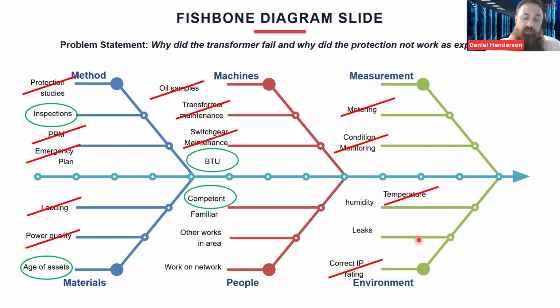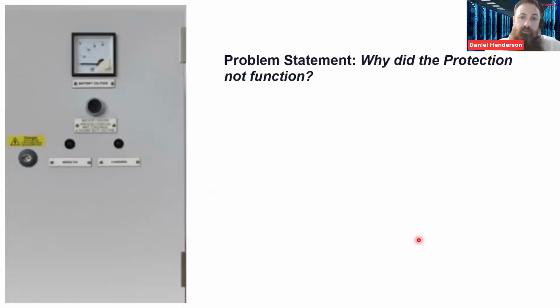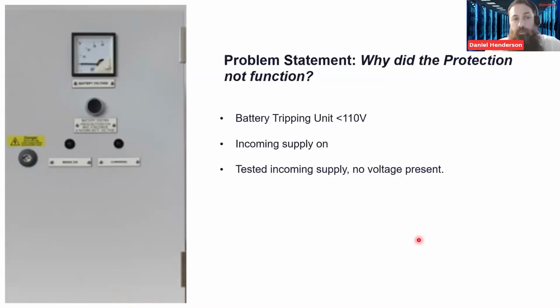Well, what I've had to do at this point is, because the transformer failed, make sure that that doesn't happen again in terms of electrical safety and reliability. So I'm trying to figure out why the protection didn't work. I've gone to check the batteries. I've checked the float voltage and I'm getting less than 110, which maybe is an impact from the downtime. I've checked the incoming supply, the fuse spur that feeds the battery tripping unit, and that's on. I've now opened the battery tripping unit up and checked the incoming terminals, and there's no voltage present. Now, this was an old battery tripping unit.